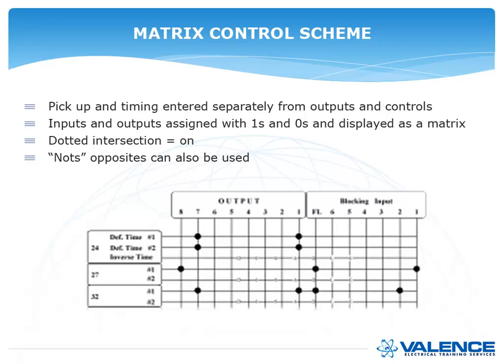The matrix scheme is very similar. This is from a Beckwith relay. This is their wonderful summary chart. And again, pickup and timing is entered separately from the outputs and controls. The inputs and outputs are assigned with 1s and 0s and displayed as a matrix, where the dots are the 1s and then 0s are not used. So in this case, that first element, the 24 definite time number 1, if it operates, it's going to operate output 7 and output 1, and nothing can block that element.